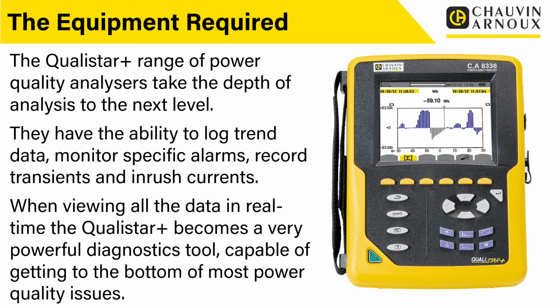Same with inrush currents - if you want to look at the inrush current for a particular piece of equipment, you can set it up and see in great detail on the screen where that inrush current fits in. So when viewing the data in real time, the Qualistar becomes a very powerful diagnostic tool capable of getting to the bottom of most power quality issues. This is why a lot of power quality professionals really like these tools, because they can use them in real time.